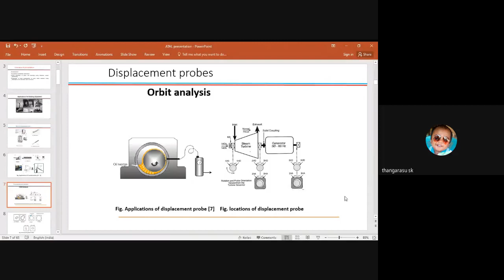Basically, we use this displacement probe in monitoring the health of journal bearing. So journal bearing, basically it is used in most of the rotating machines like turbines, IC engines and all. So to monitor the health of a journal bearing, we use displacement probes. Those displacement probes are mounted at a particular angle, 45° from central axis, which will give the details of operating condition of journal bearing. Let us see how.